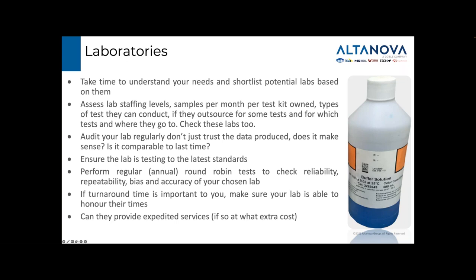out of the lab. In a recent study of just DGA on three laboratories, all three labs provided DGA data outside of plus or minus 20% of the actual levels. This level of inaccuracy means ratio analysis can be invalid, which also means the interpretation and appropriate maintenance will be inaccurate.